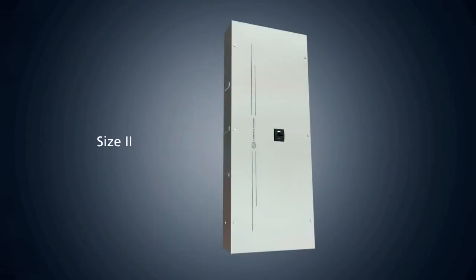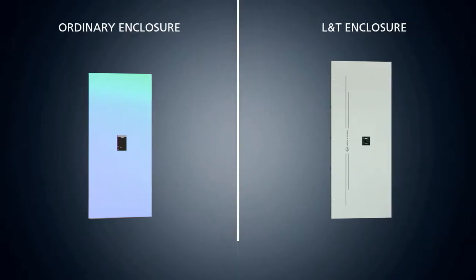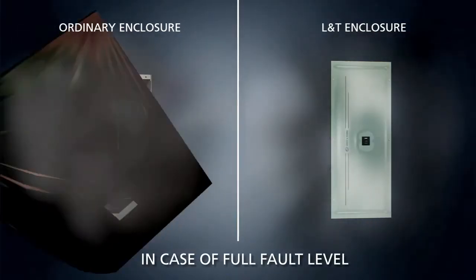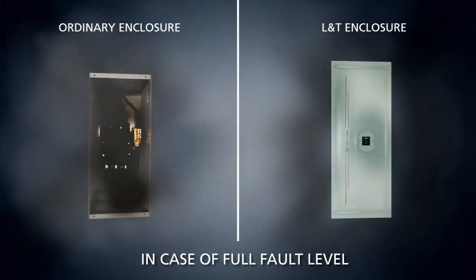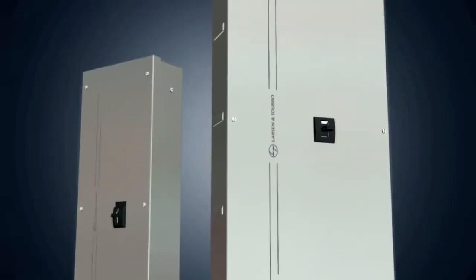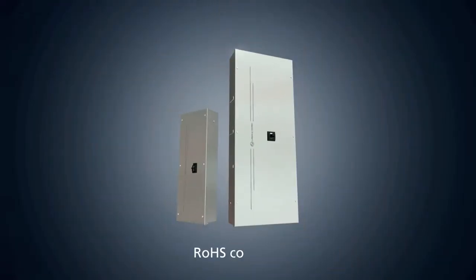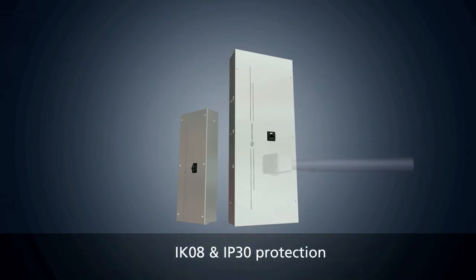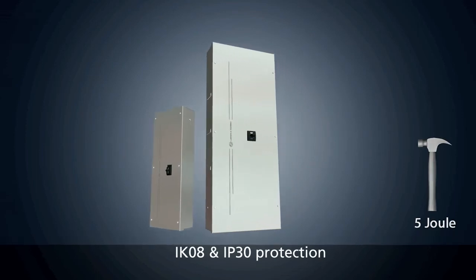Size 1 can sustain fault level up to 36 kiloamperes and size 2 up to 50 kiloamperes, which implies that enclosure and door remain intact for such high fault currents. These are sturdy as well as RoHS compliant. The IK08 protection safeguards these enclosures from any impact up to 5 joule.